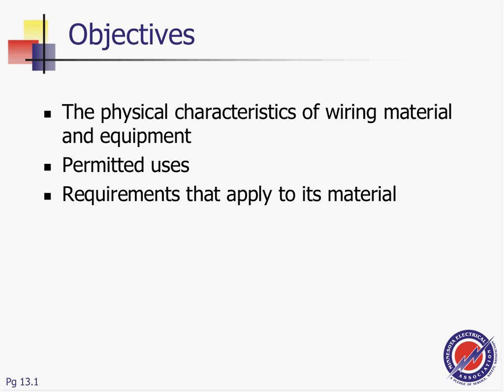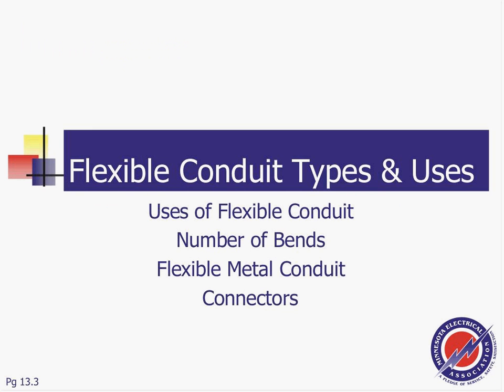We're going to talk, guys, about the physical characteristics of wiring methods and equipment for flex, the uses permitted for the types of flex, and the requirements that apply to installing the flex. So these are a few things that we will be touching on tonight. We're going to talk about flexible metallic conduit, liquidtight flexible metallic conduit, and that's the second one. And the third one, flexible nonmetallic conduit, with three types that they have. I'm going to do my presentation and flash my NEC code book here, and when we're done with this, we'll do some exercises, probably about how many conductors you can fit in them and so forth. And then after that, we'll touch on the cabinets and so forth.